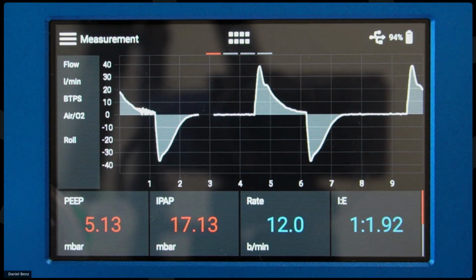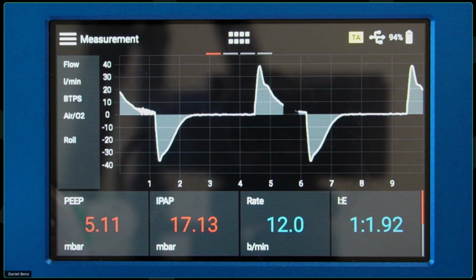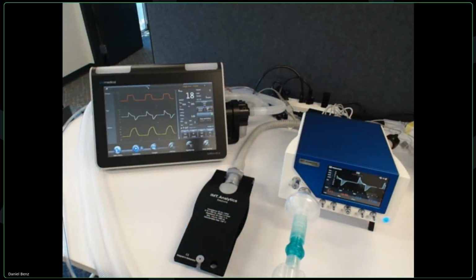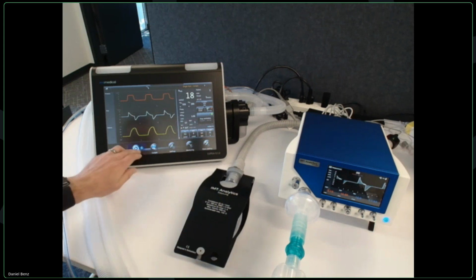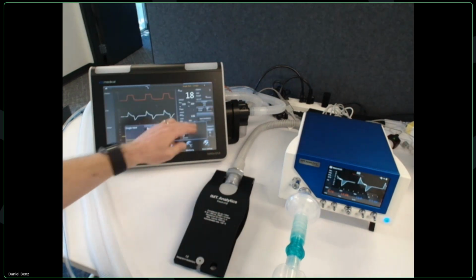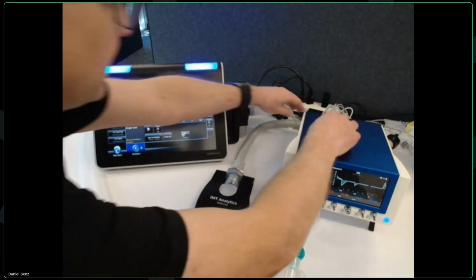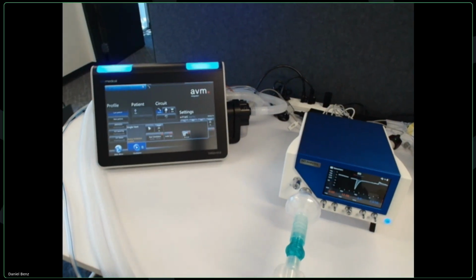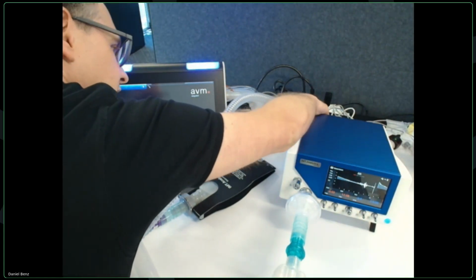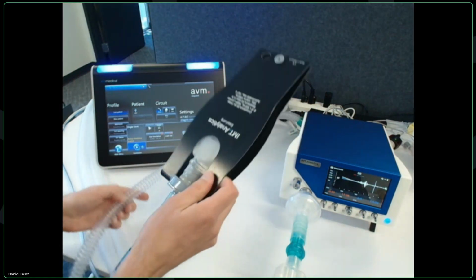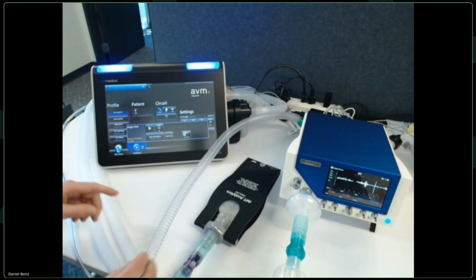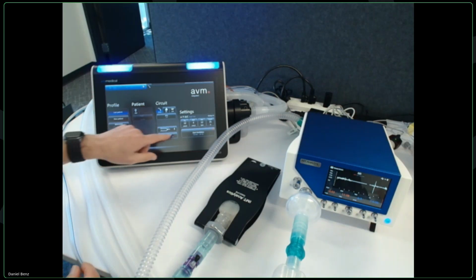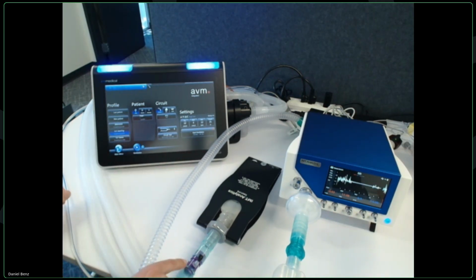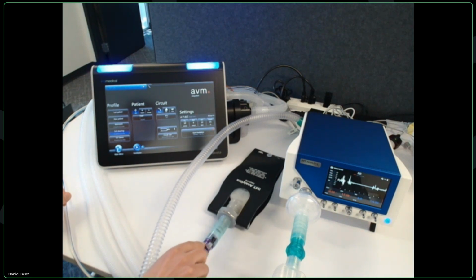So now let's change the application here. And I'm going to show you what I'm doing. First of all, I stop the ventilation real quick, and I'm going to change to a little bit of a different setup here. Going to disconnect my test lung here and connect a different circuit. So this is something you would typically see when you test BiPAP ventilators. So now I have a circuit system connected with a defined leakage here in front of the test lung.